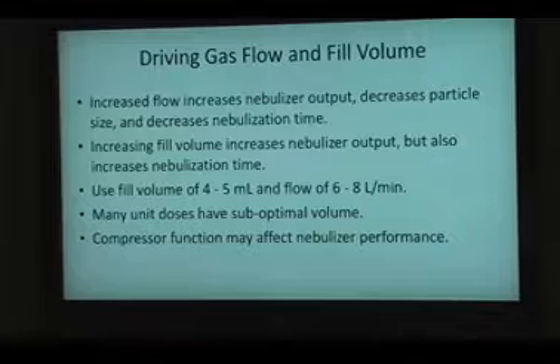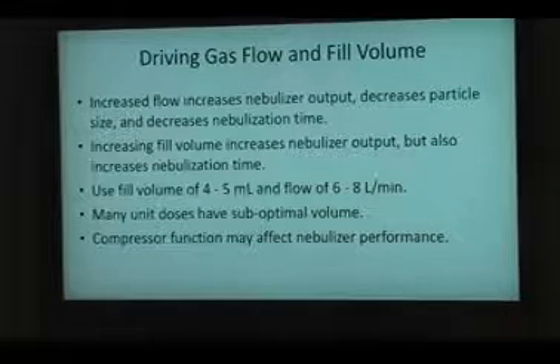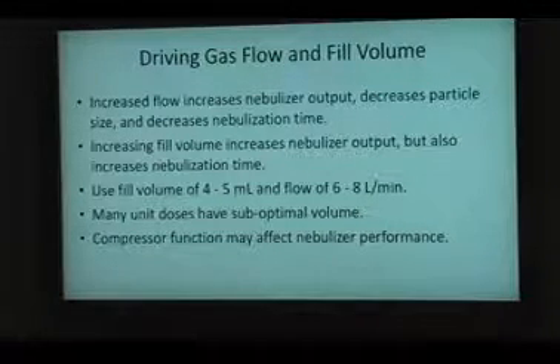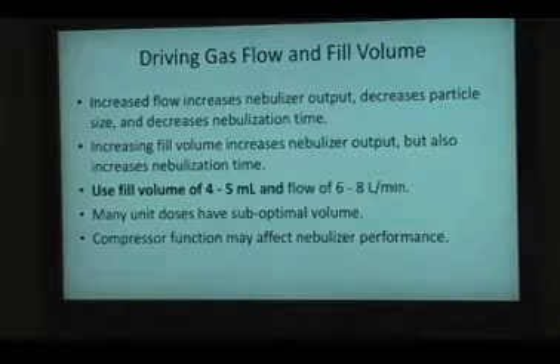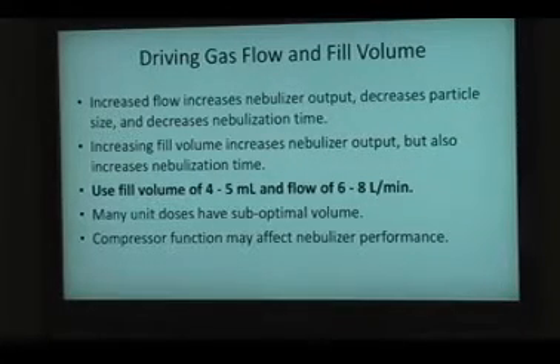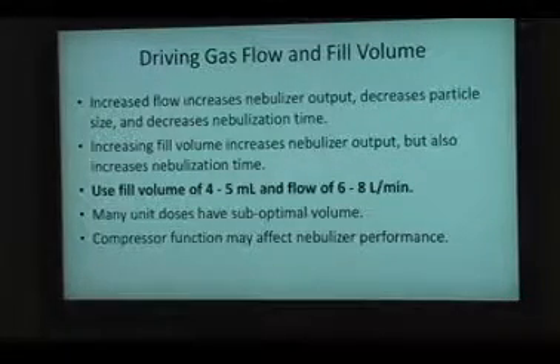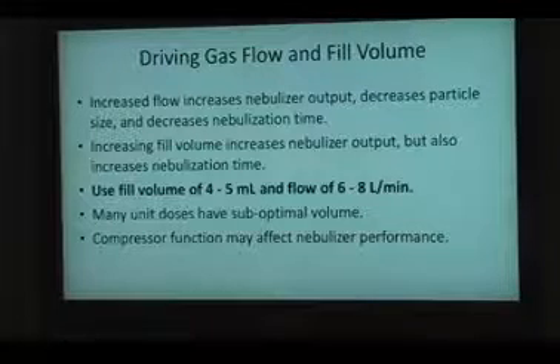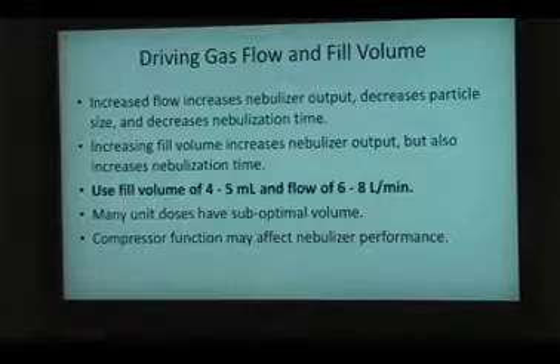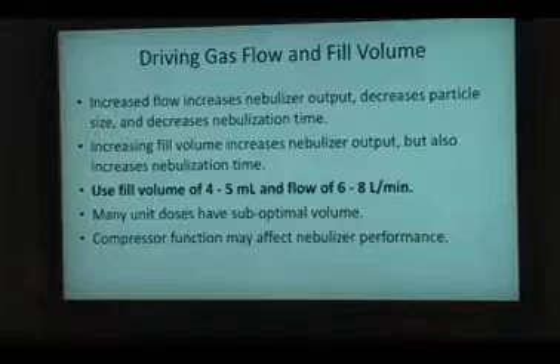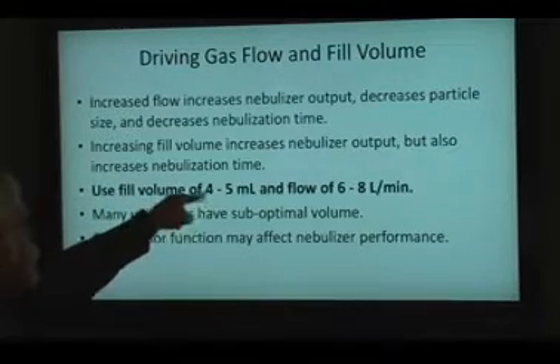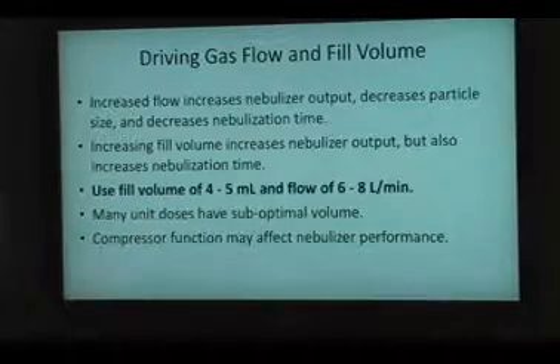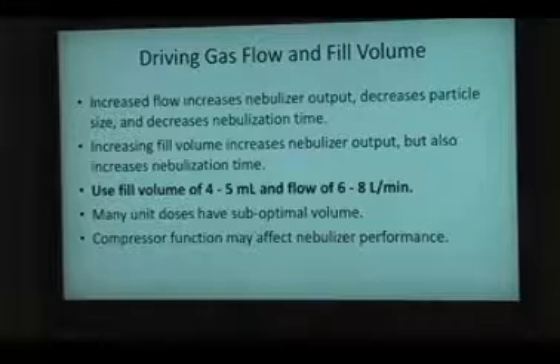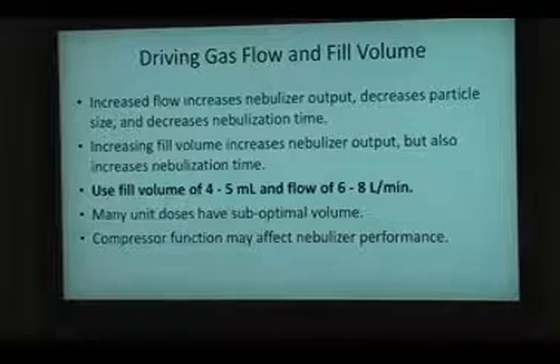So we talked about this in some detail the last time I was here about the importance of driving gas flow and fill volume with jet nebulizers. So the typical jet nebulizer, there are some exceptions to this rule, but the typical off-the-shelf jet nebulizer works best at a fill volume of about 4 to 5 milliliters and a flow of 6 to 8 liters per minute. So why might that be an issue?